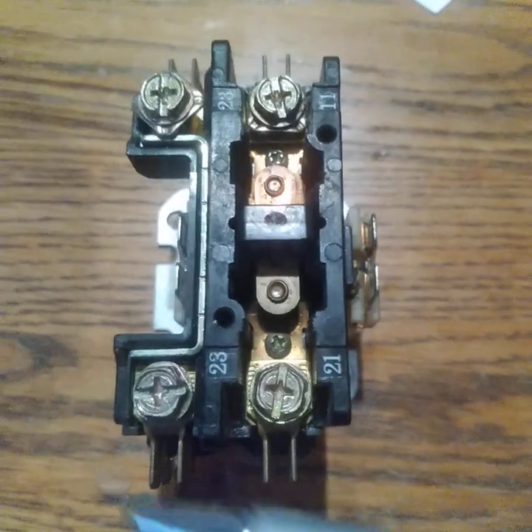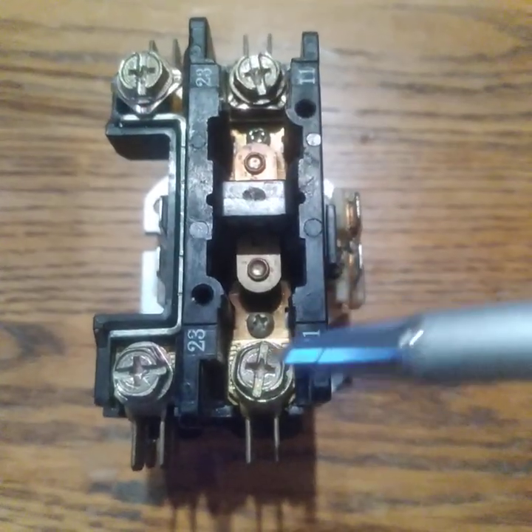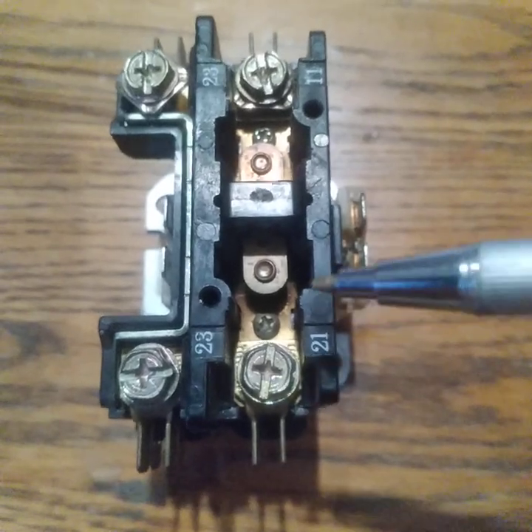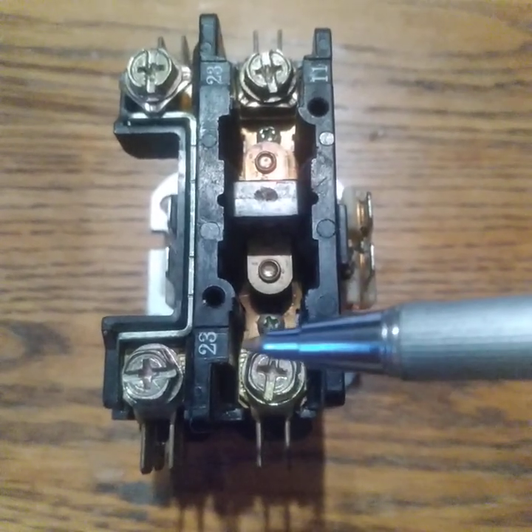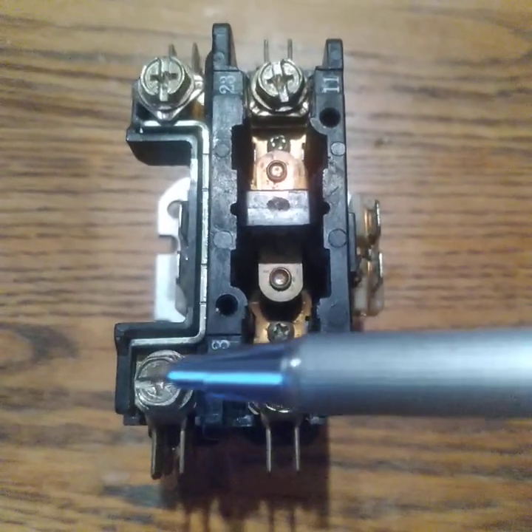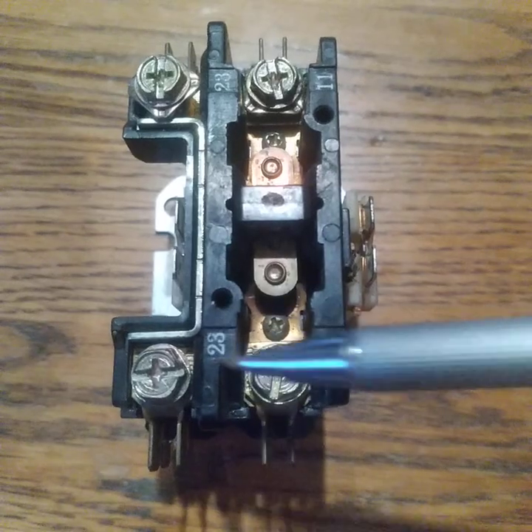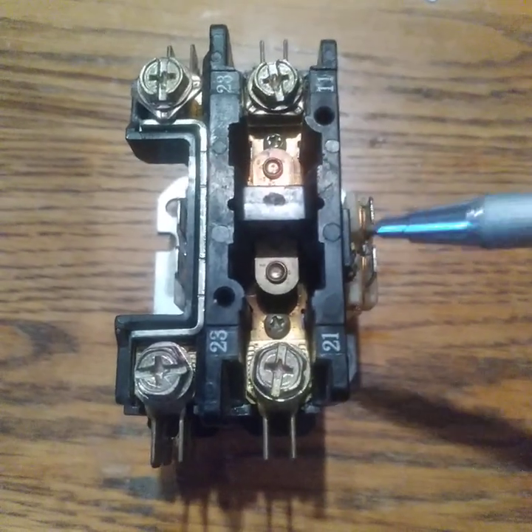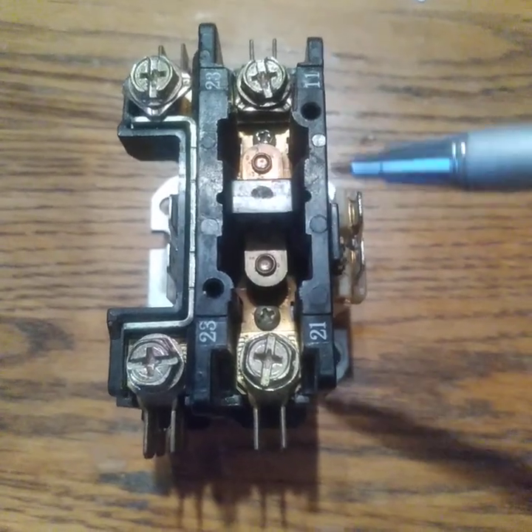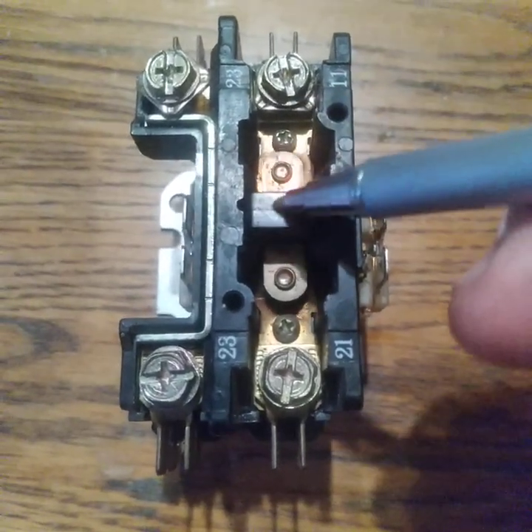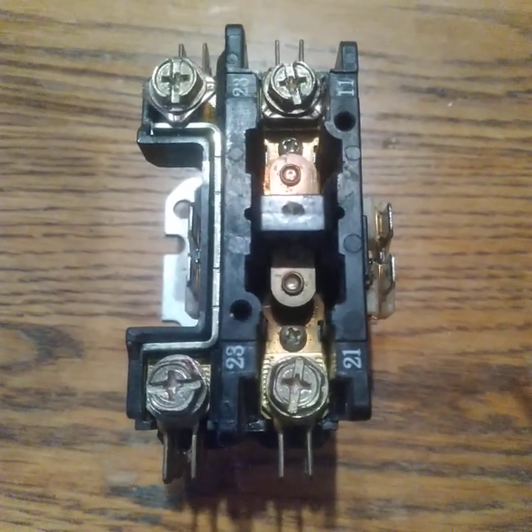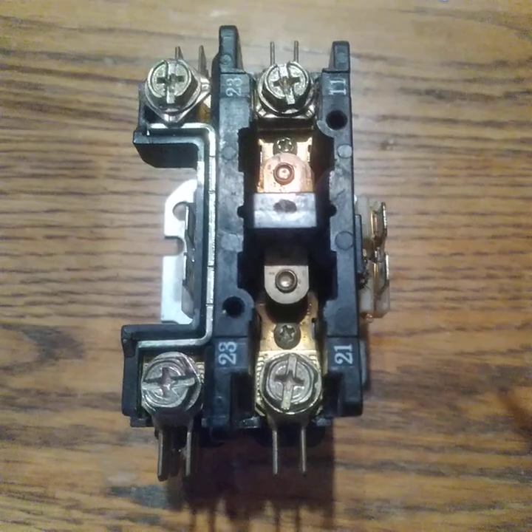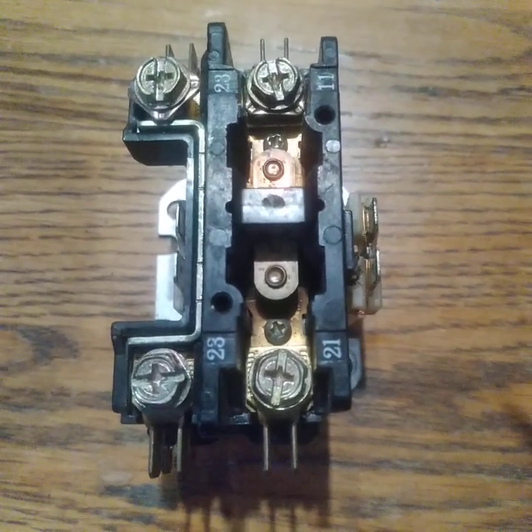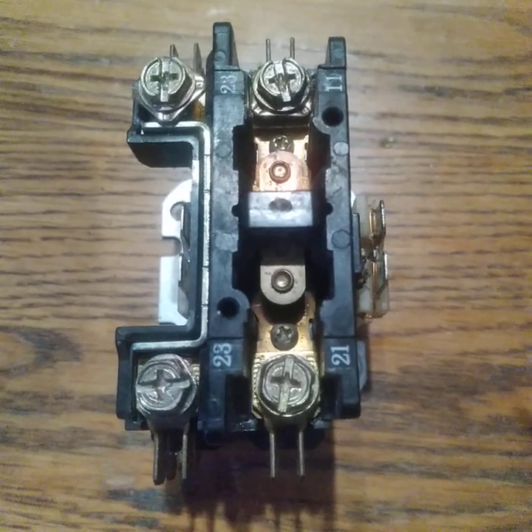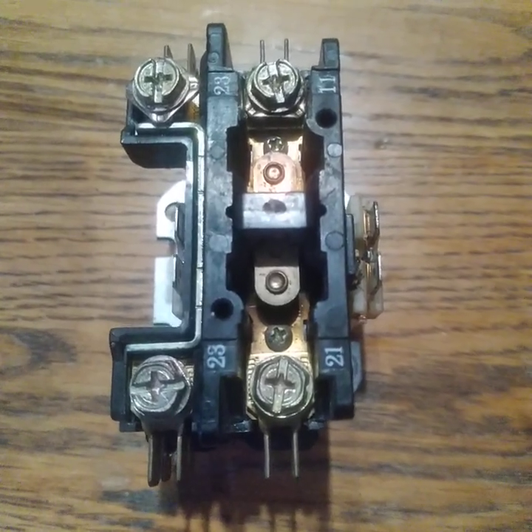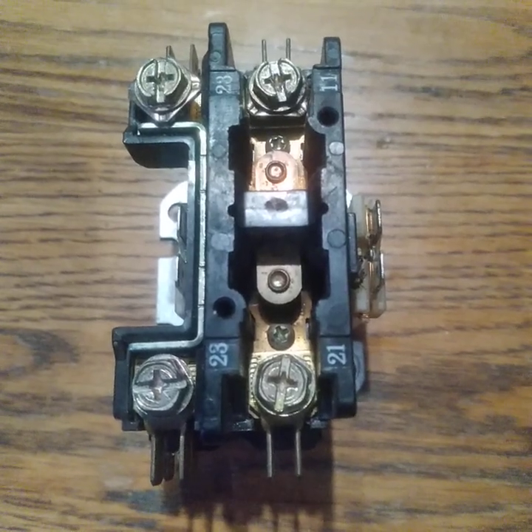But again, L1, L2, T1, T2, 240 volts. The 240 and the contactor will convey the electricity from this side to this side. Once the low voltage is hooked up here, it pulls the coil in, pulls the plunger in, the contacts meet, and it's that simple. So if all things are equal and working properly, your compressor and your condenser fan motor should operate. An HVAC contactor for the condenser.